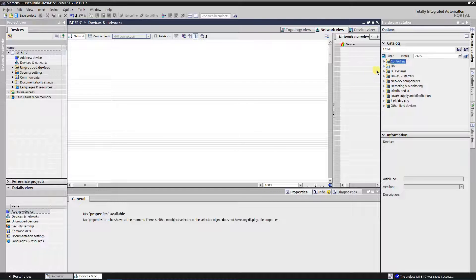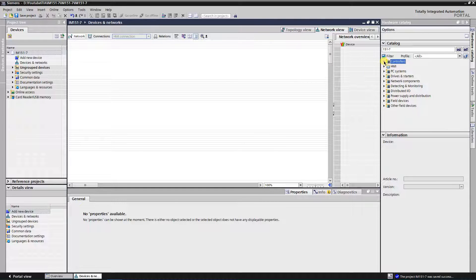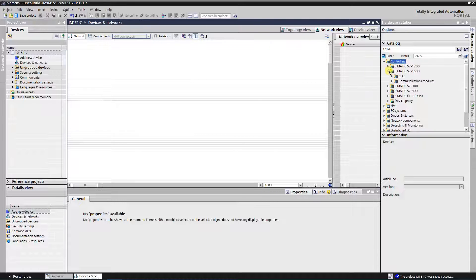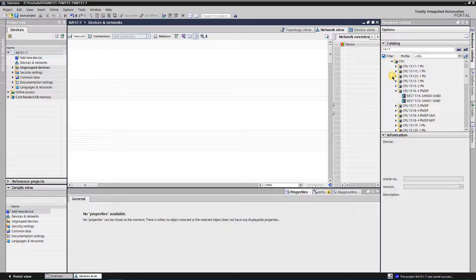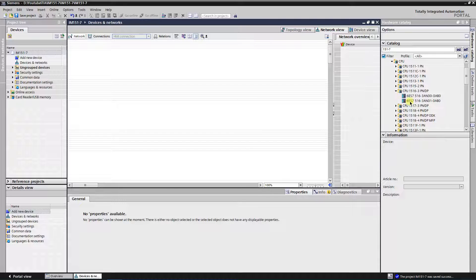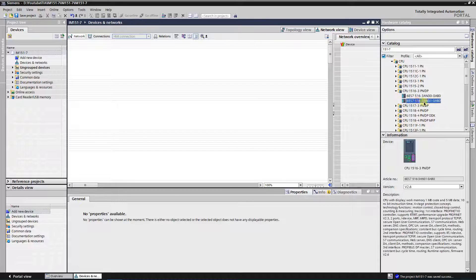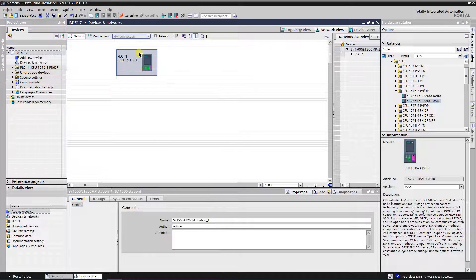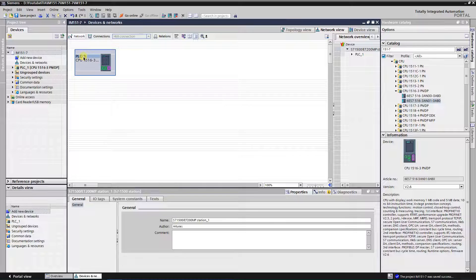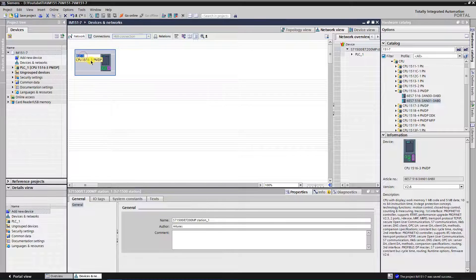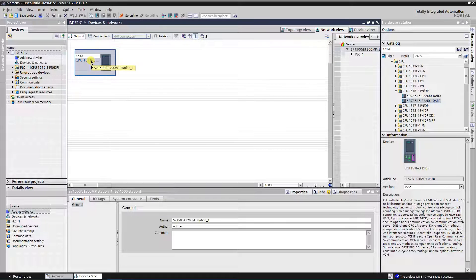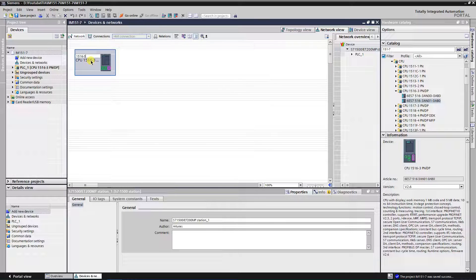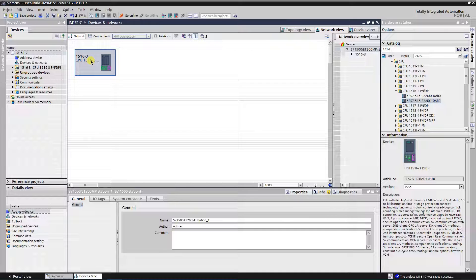In the hardware catalog expand controllers folder, then S71500. Find your CPU in the folder, select it, and then drag and drop it onto Devices and Networks window. My CPU is 15163 PNDP. I am going to name it as 1516-3.